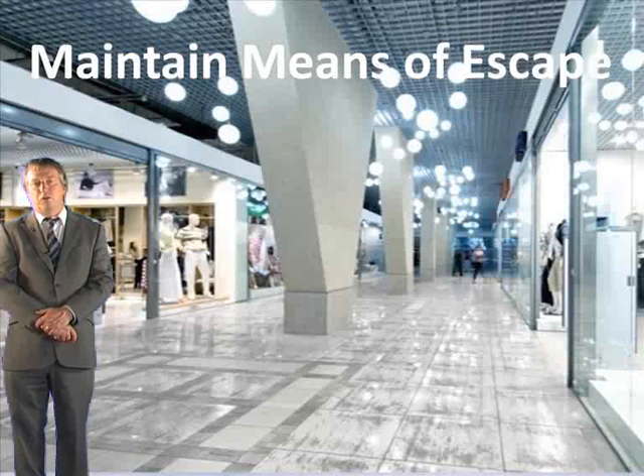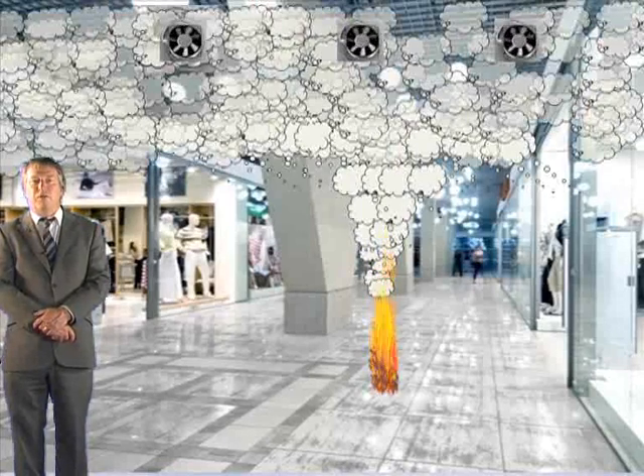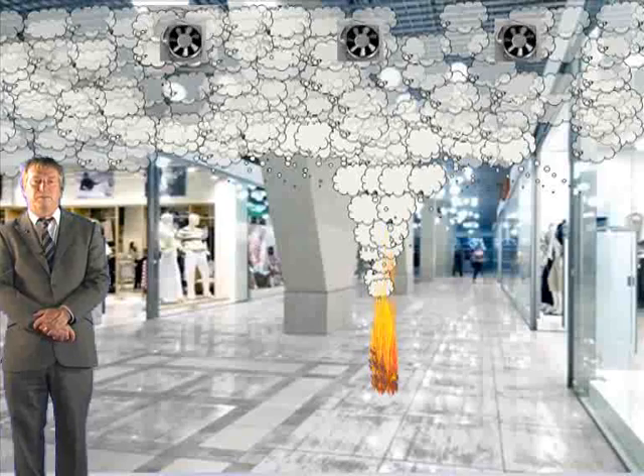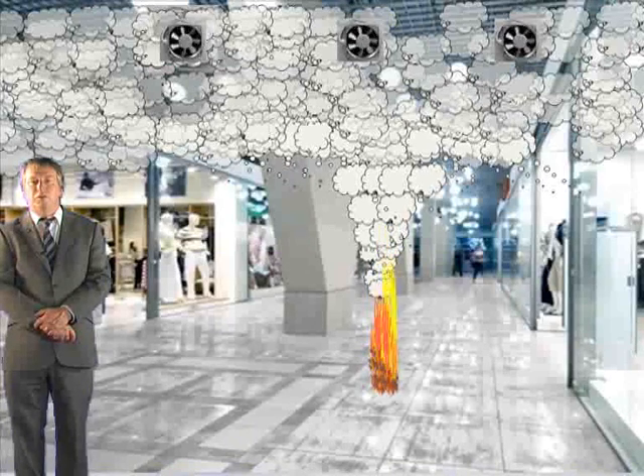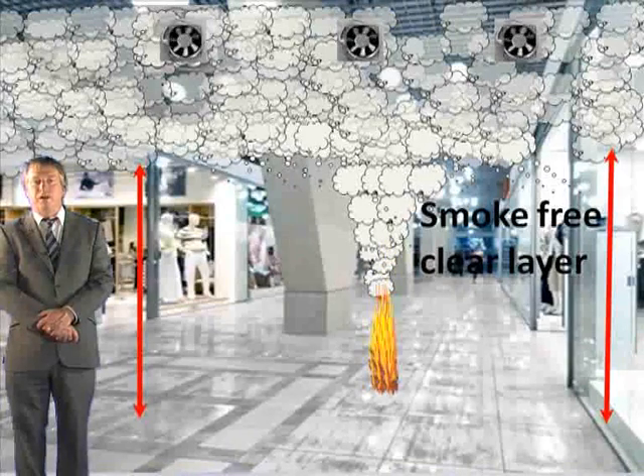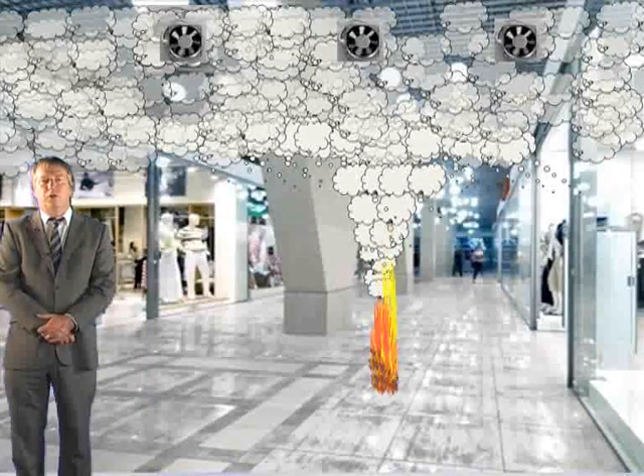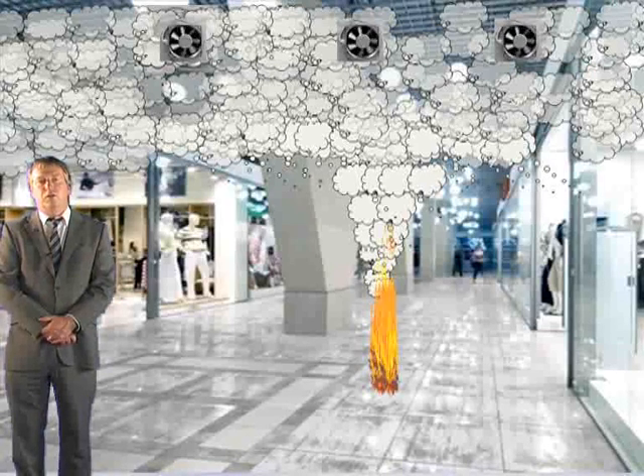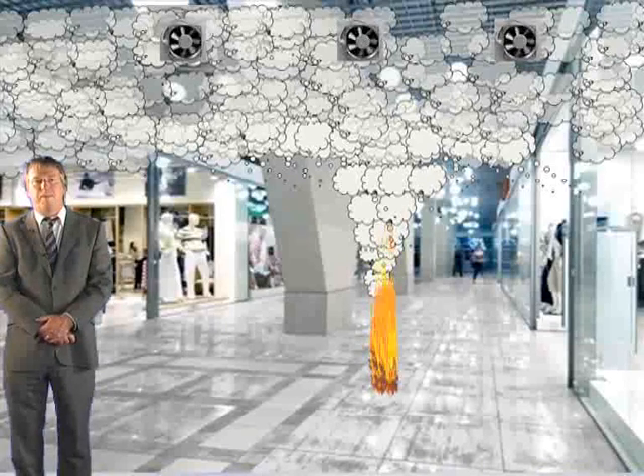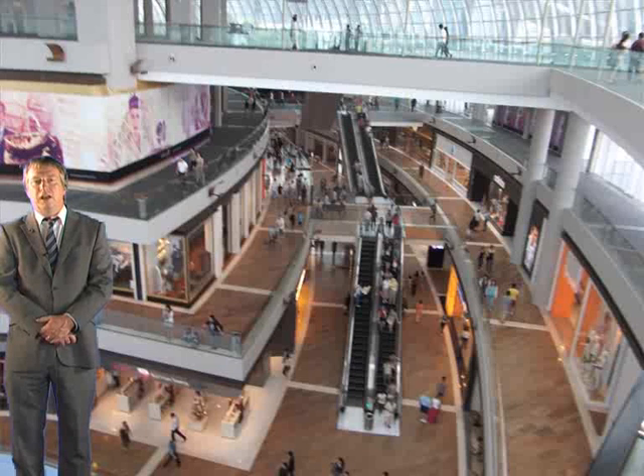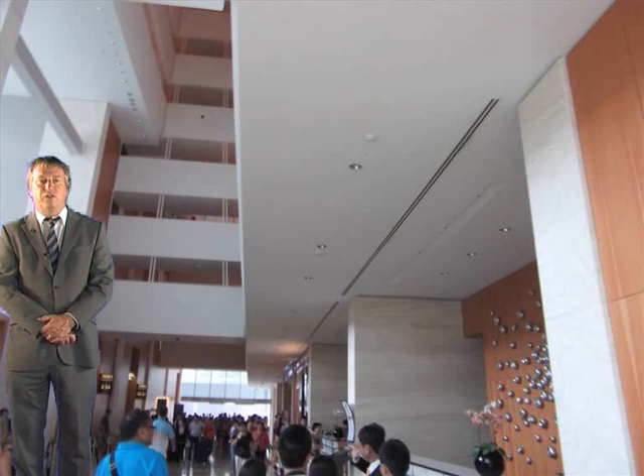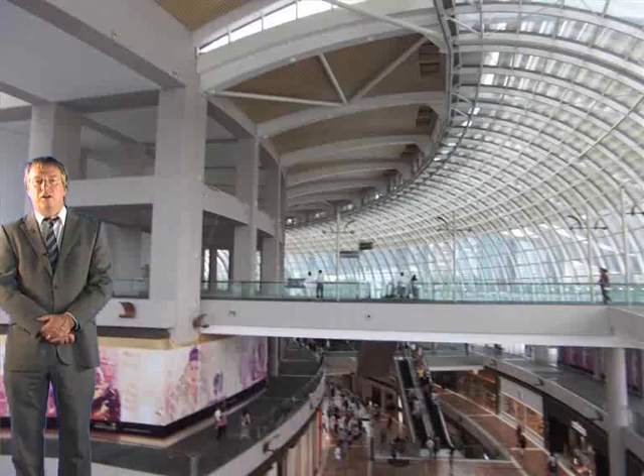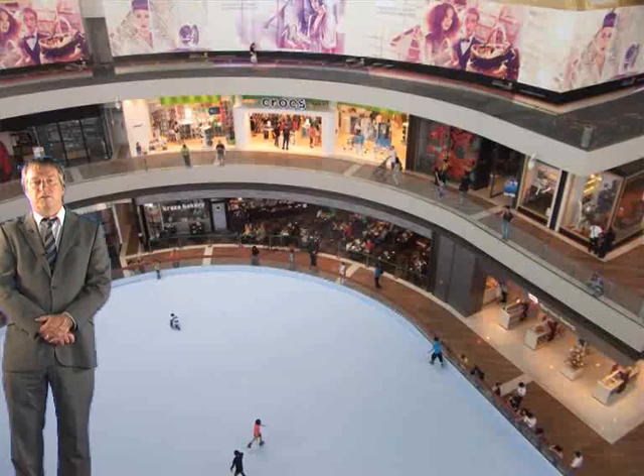Now, the primary reason for installing a smoke control system is for protecting means of escape, and this may allow freedom of design to architects and designers. This objective is to achieve a desired smoke-free clear layer beneath the smoke layer. This approach is commonly used where the purpose of the smoke and heat exhaust ventilation system is to allow the continued use of the escape routes which are in the same space as the fire. For example, this may include enclosed shopping malls and many atria or large single-storey spaces such as public assembly buildings.